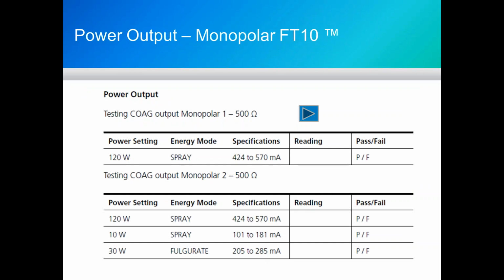One significant change that the service manual has allowed for with the FT10 is, as you remember, you used to do every output test on monopolar 1, every output test on monopolar 2, every output test on the UFP port. There is but one RF generator within the unit. There is some steering circuitry that determines what port the energy is delivered to.